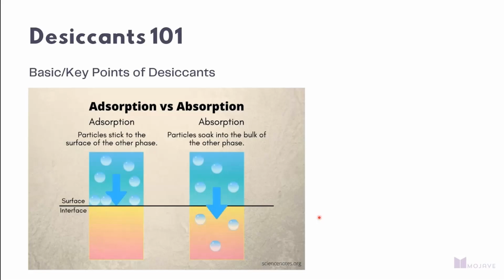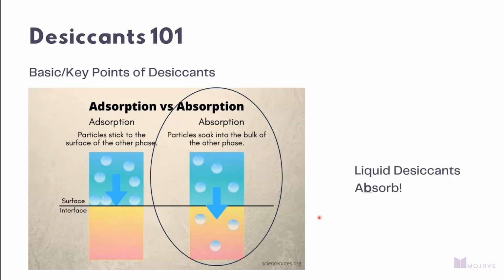So I've thrown around the words adsorption and absorption. Let's define those briefly. Adsorption is where particles stick to the surface of another phase. This is what solid desiccant wheels do. You have water molecules, they stick to the surface of a solid desiccant material. Liquid desiccants use an absorption process with a B, and that's where we have those water molecules coming into that desiccant puddle from my example on the last slide, growing that volume. And as they release that moisture, the volume shrinks. So liquid desiccants are using an absorption process with B.